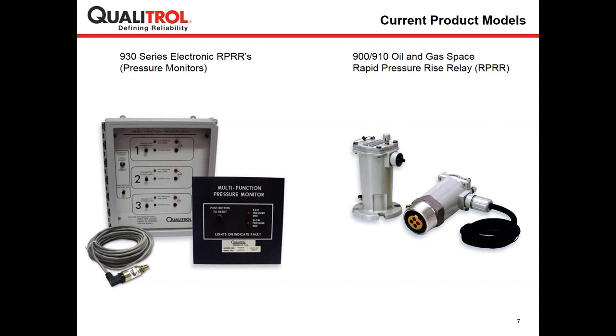Now for those, we have various styles for mounting. You can see threaded, and flange. They can be mounted horizontally, vertically, and have a variety of different connection styles. But all of these units that you see on your screen are there to protect your asset in the event there is a quick change of pressure. Sudden pressure relaying can be used synonymously with rapid pressure rise relay. So you may see and hear both of those acronyms. SPR and RPR are throughout the presentation.